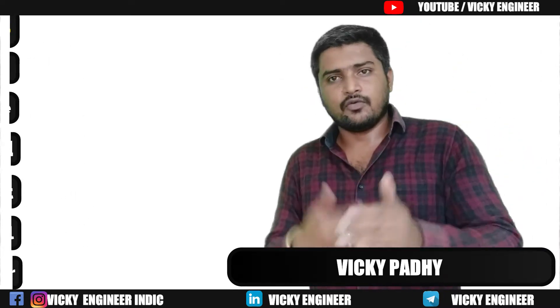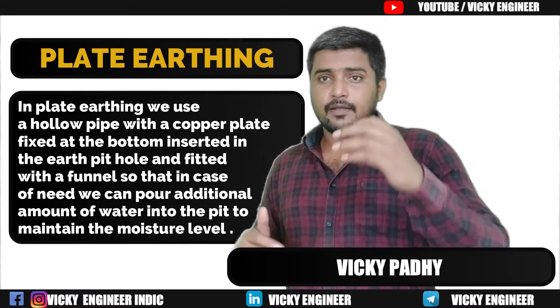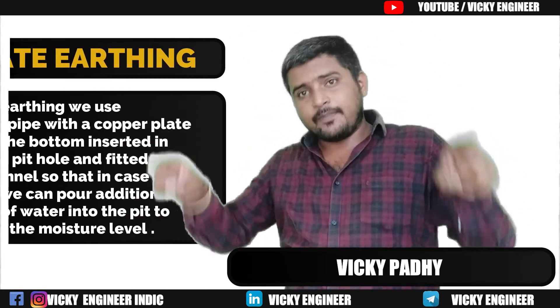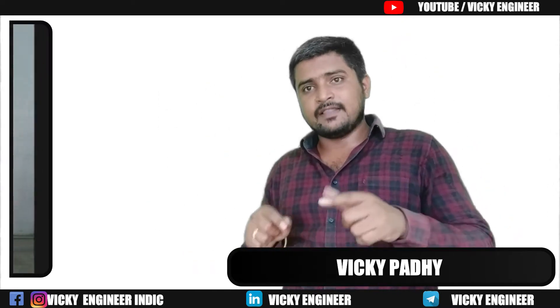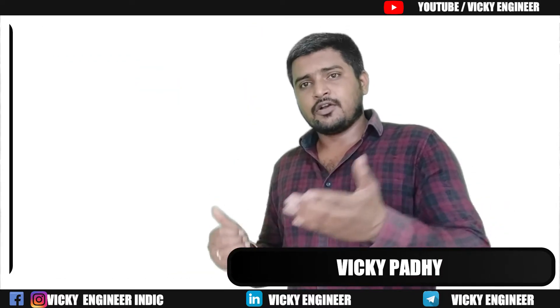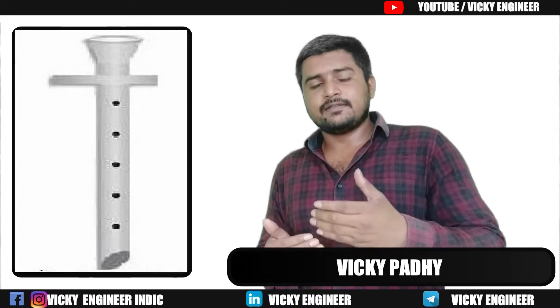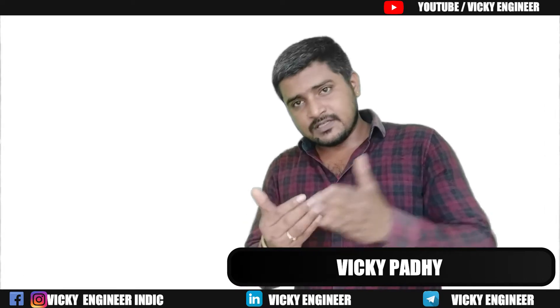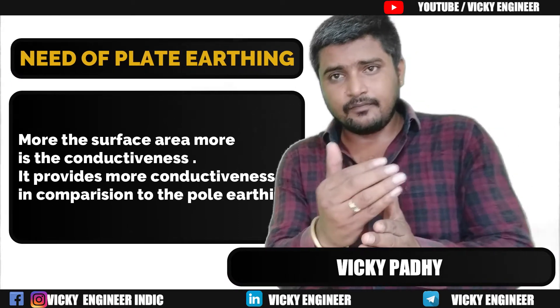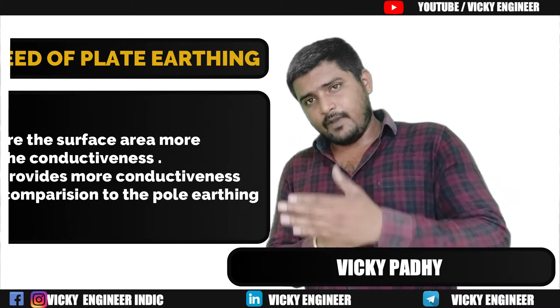You should maintain at least 4 layers, or you may go beyond that for good performance. Next is plate type earthing. Plate type earthing is where we insert a plate or earth electrode into the earth pit with a copper plate welded or faced with it. The reason behind this is that the more surface area facing the conductive materials, the more will be the conductivity.